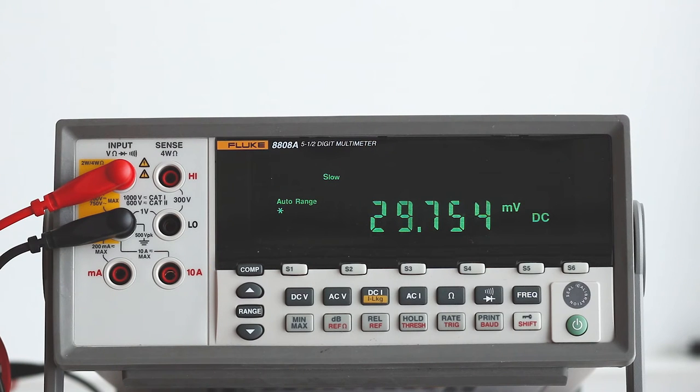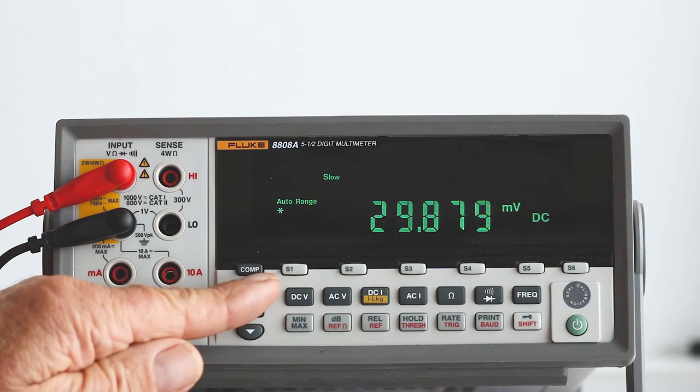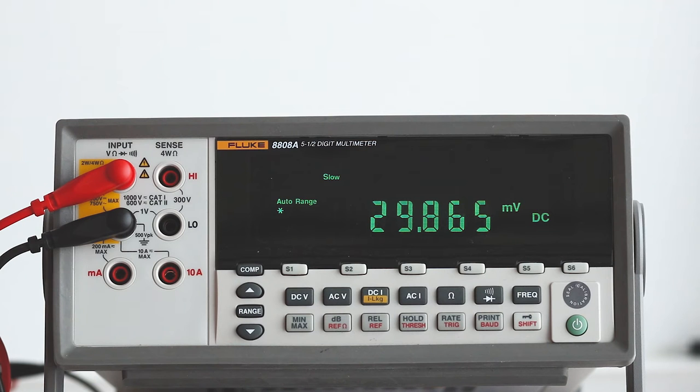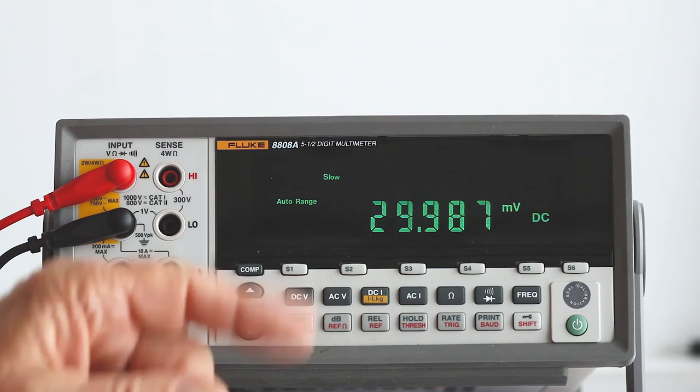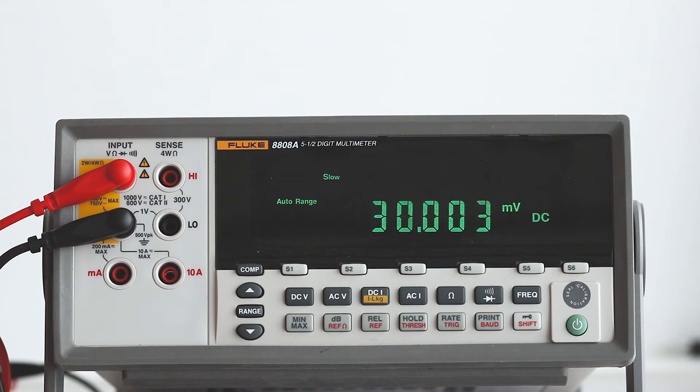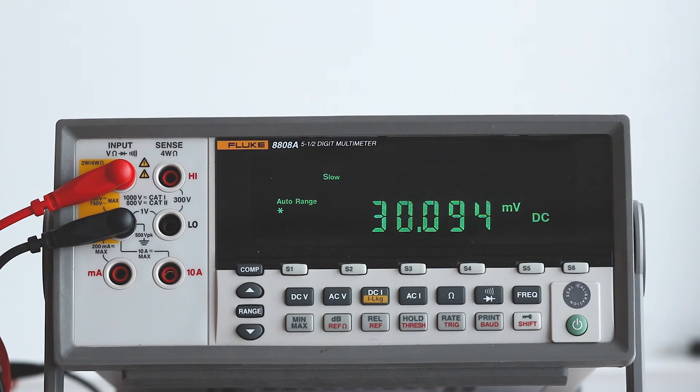Just after the manual range control is DC volts. Notice that when the probes are not connected to an energy source there is a fairly low reading that seems to fluctuate. This is called phantom or ghost voltage and it is a consequence of the fact that we are using a very high impedance meter, meaning that it places a negligible load on the circuit being tested.